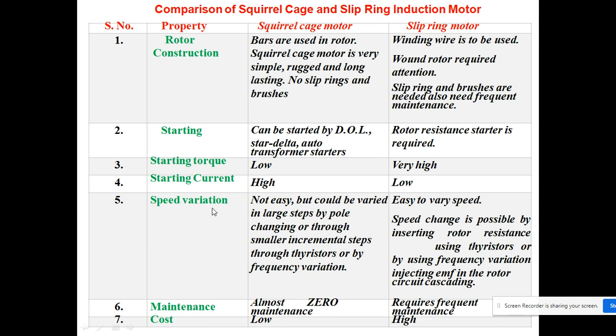low. And if we are talking about speed variation, in the squirrel cage it is not easy. It cannot be varied in large steps except by pole changing, or in smaller incremental steps through thyristor or by frequency variation. Here it is easy to vary the speed. So speed variation is easy in the slip ring motor, or we can say the phase wound motor. Sorry.